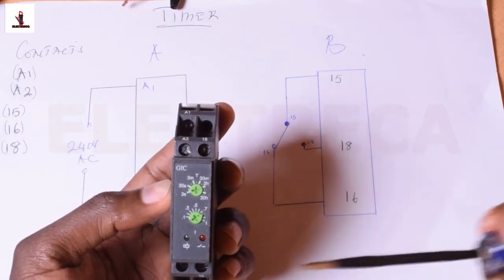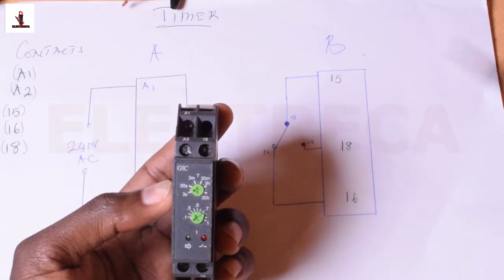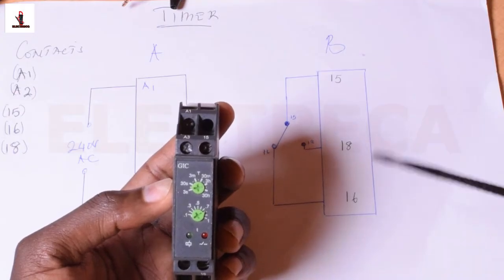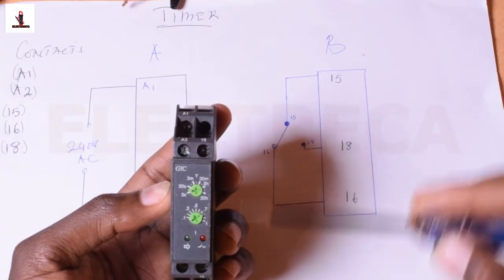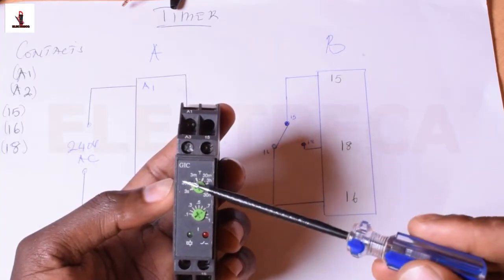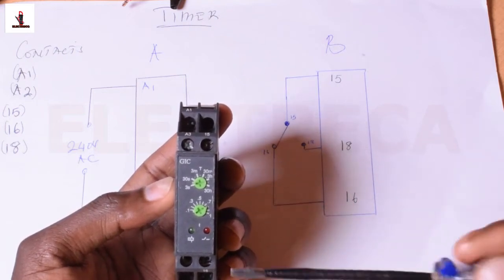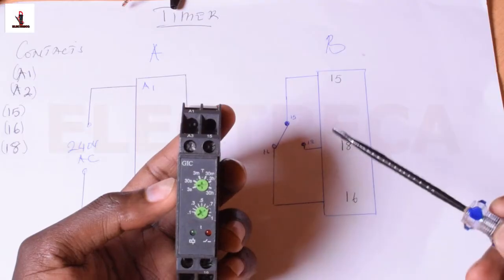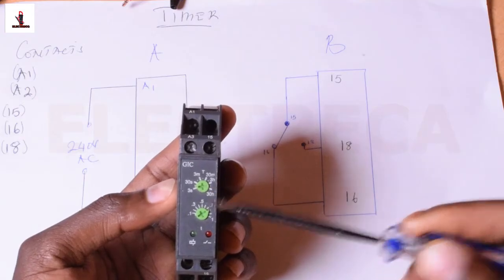You know when the generator starts, it needs at least some few seconds—at least 30 seconds—for it to attain its maximum speed, which will help it to attain its operating frequency. And then also all the parameters, the voltage and things, are all in sequence and okay. So you give it 30 seconds or slightly more; that one is enough for your generator to have aligned all the parameters.